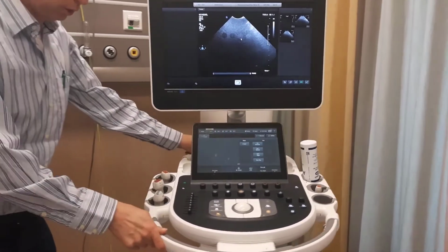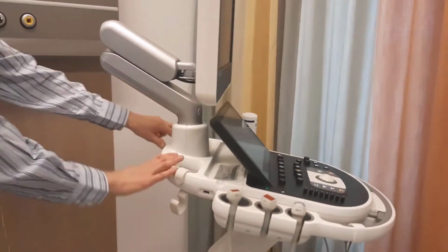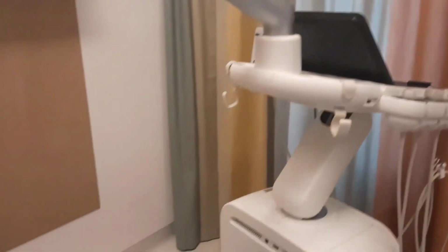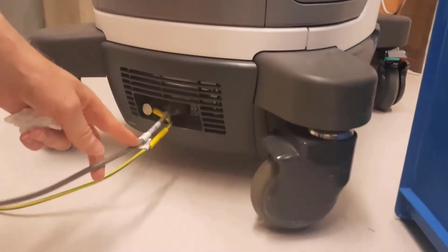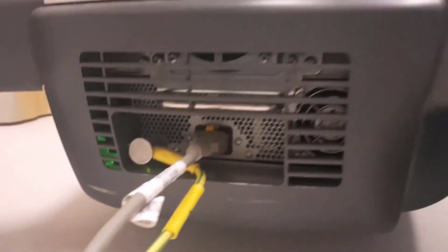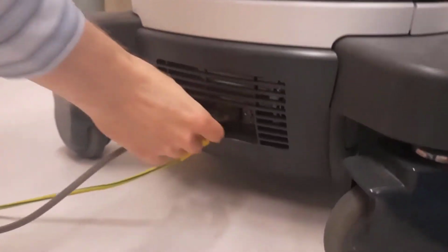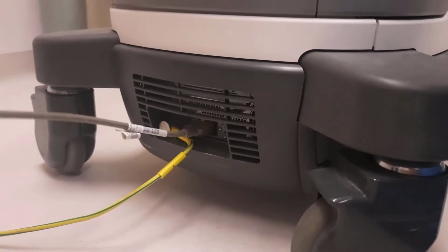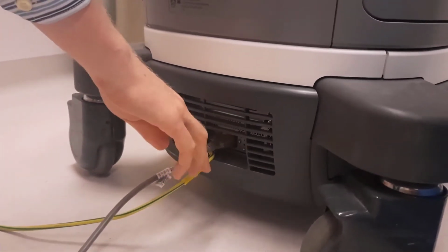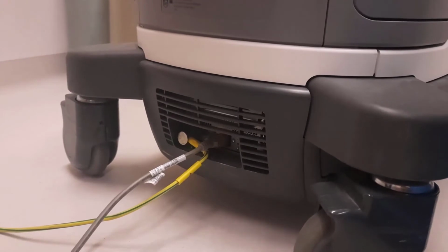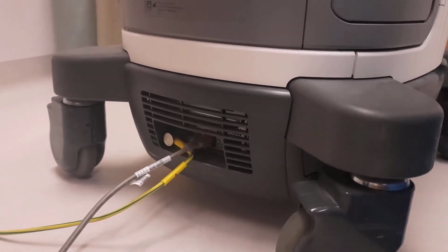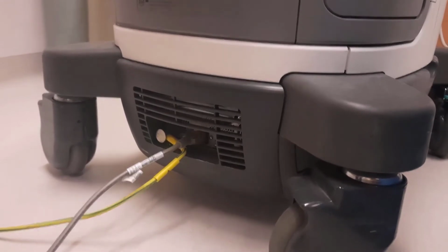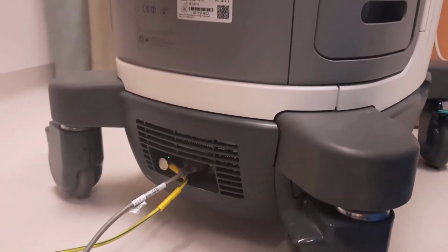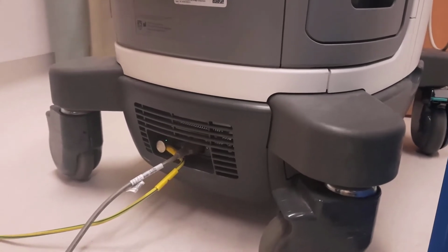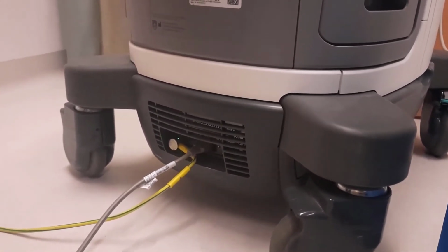Another thing you can check is the power cable. The power cable goes in the back of the equipment. Sometimes this is fixed in the connector, and when you pull at this, the cable can get damaged at that point, and that's a possible chance of short circuit. So that is also a yearly checkpoint for us.